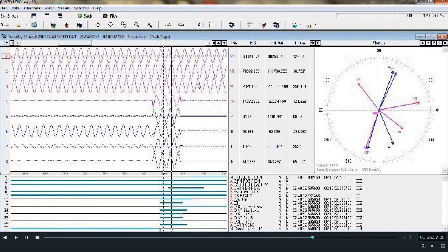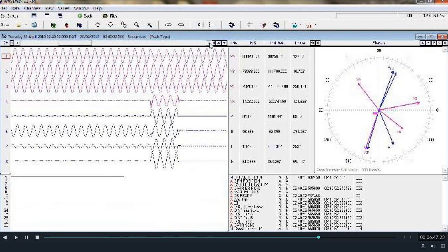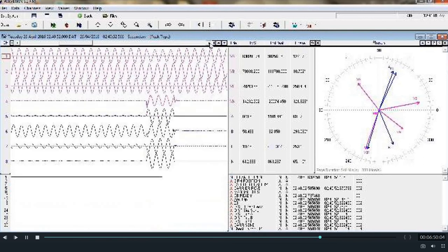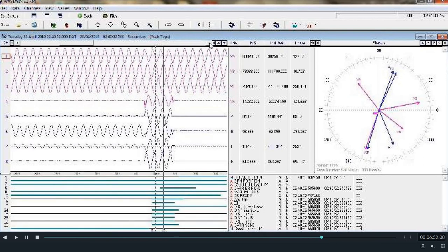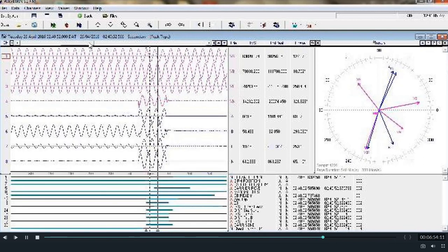If we see here, there is a wrong indication showing continuously, that is manual close. This indication is wrongly assigned to this relay. There is much more information that we will be able to get from these digital signals of the DR.